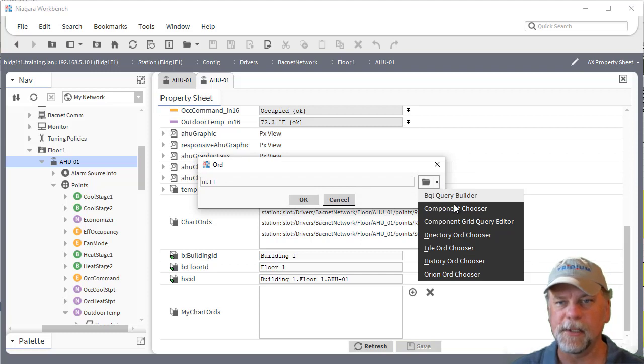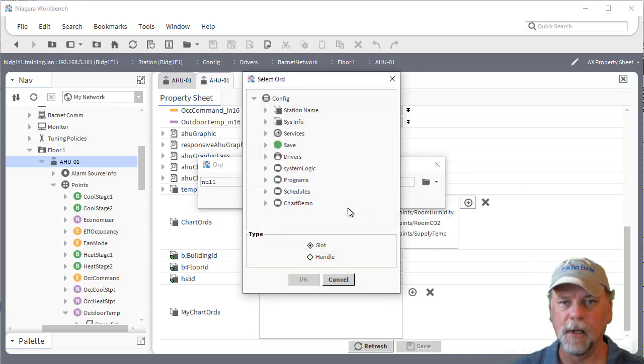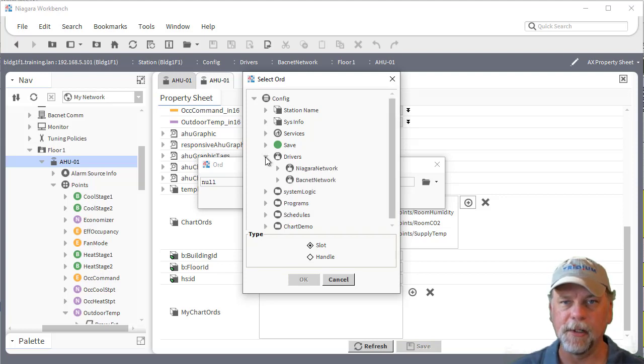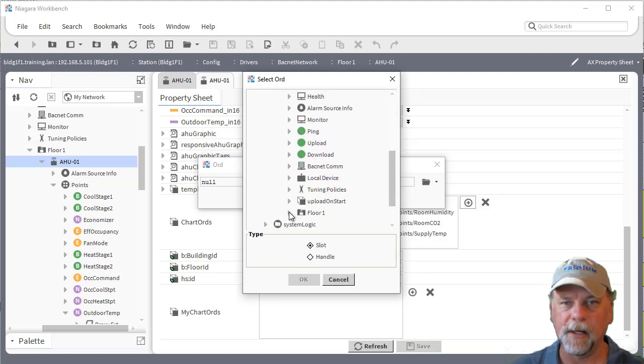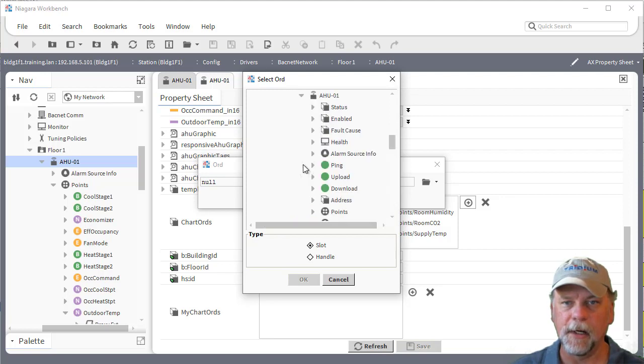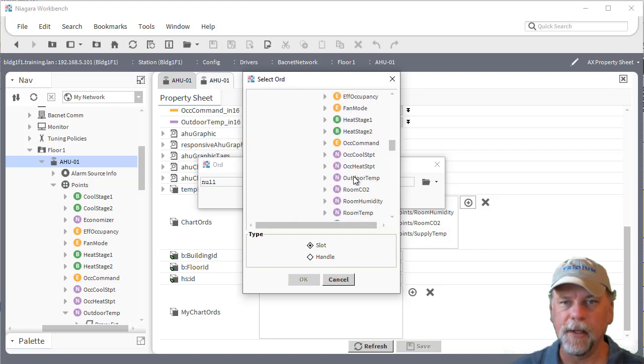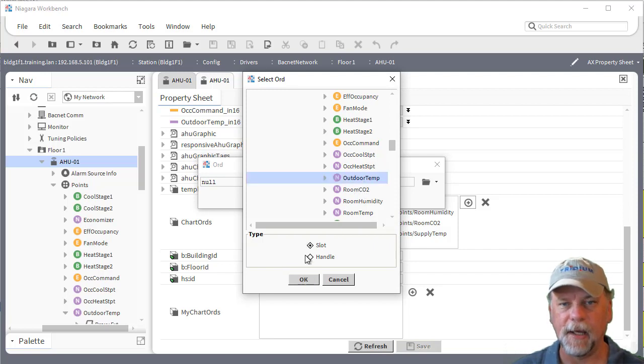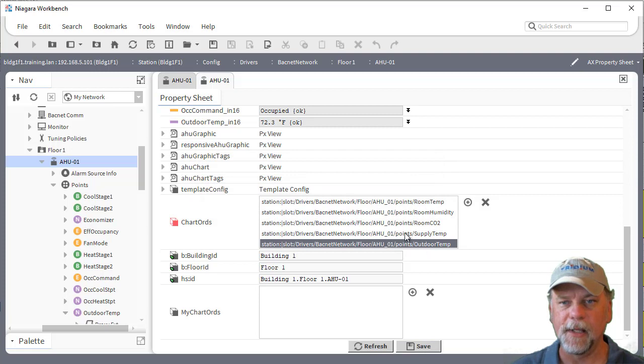You can add ORDs here by clicking on the plus symbol which opens up an ORD selection dialog. Then you can use that to pick components or histories or whichever that you're trying to map to here. In this case I could go under the BACnet network to floor one air handler one points and then select the outdoor temp.